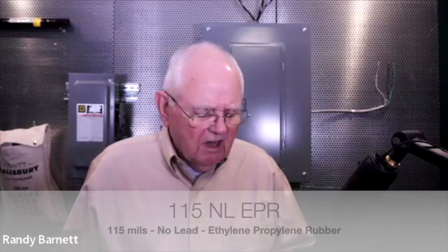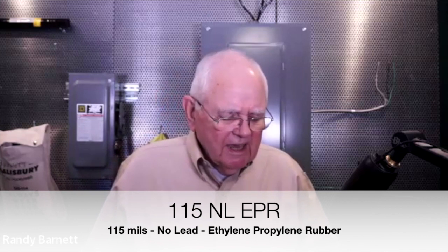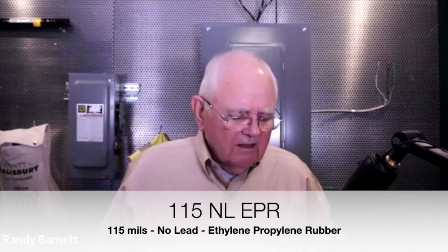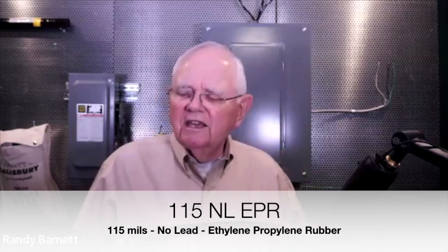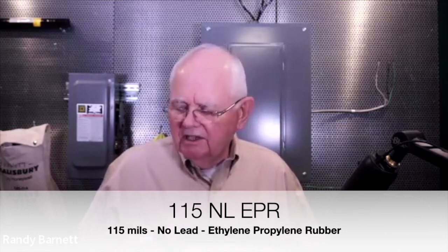115 NL-EPR. NL-EPR tells me that there's no lead in the insulation. And the insulation is the white material that you see here, the main layer of insulation, I guess we could call it. It's a dielectric insulation. It's ethylene propylene rubber, which is a synthetic type of rubber. And it's also called a thermoset insulation. It has some excellent insulation properties as well as physical properties.